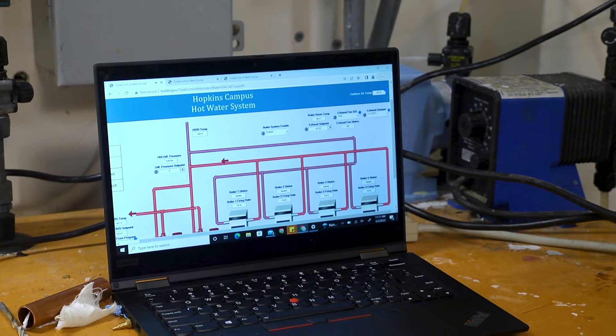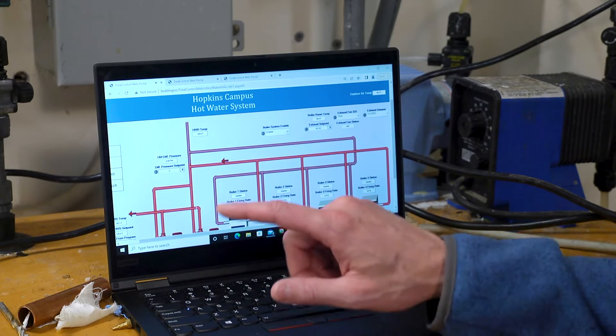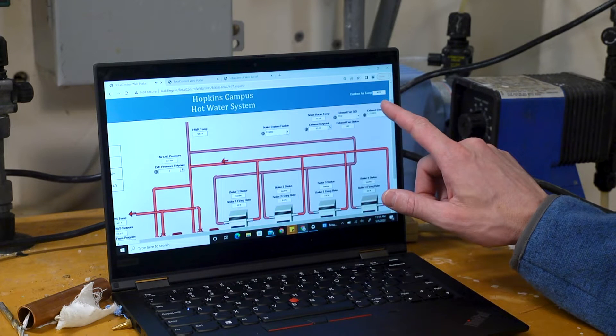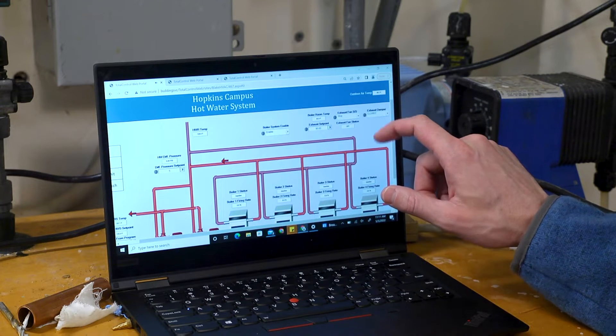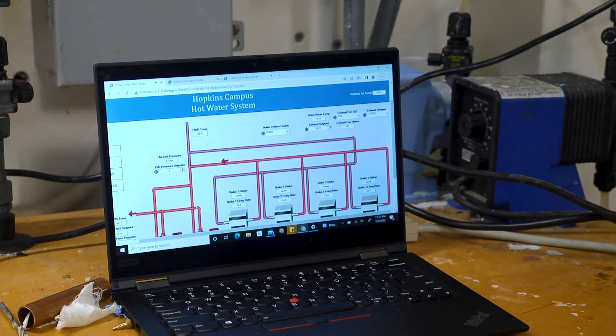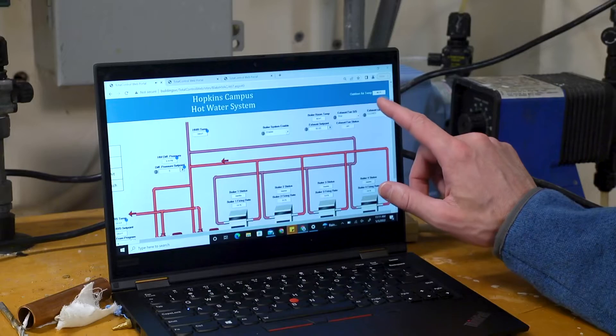Here we have a heating hot water system and we have a bunch of sensors. A critical one would be the outdoor air temperature sensor. The outdoor air temperature, depending on its reading, will dictate whether or not the system runs and when it's running, what temperature of water we're going to be operating at. So it's a pretty critical sensor. So it's good to do a sanity check every so often on that sensor.